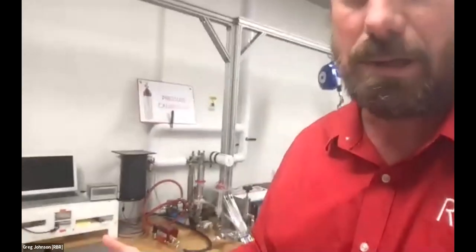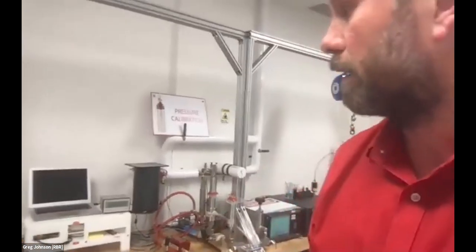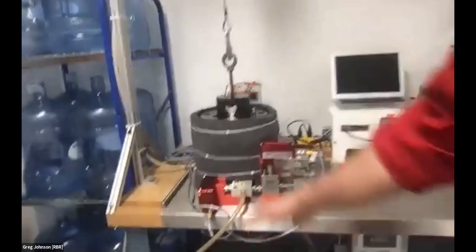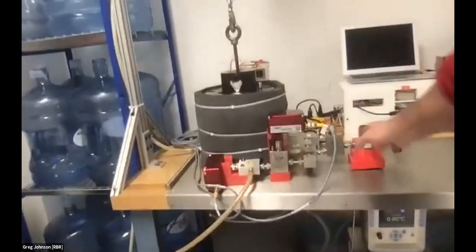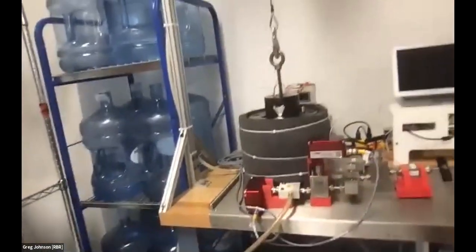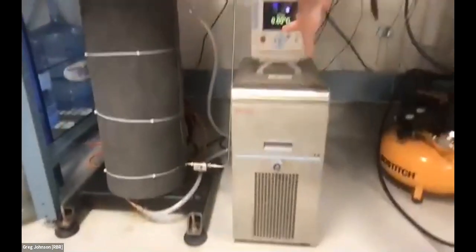This one is compressed, pressurized hydraulically. So all of these actuators and valves on the outside are used to drive in pressure and release it. And likewise, we have an insulated jacket and a chiller, which keeps it cold, because for deep water calibration, we particularly want to verify the performance at oceanographic temperatures, kind of 2 degrees when you're down at the bottom. I'm going to walk over to the conductivity area.